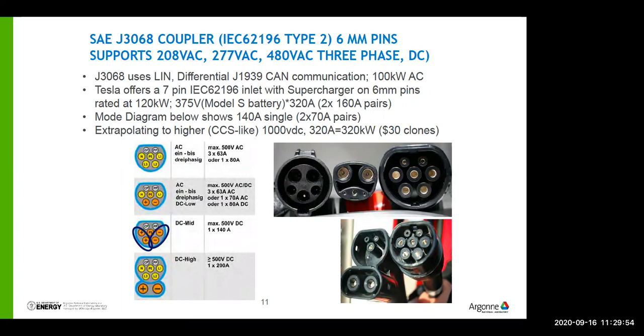That 320 amps at 1,000 volts makes it 320 kilowatt. This, again, not an NRTL listed one, but a clone. These connectors can be had for $30, so it's a very low cost way to get a lot of power. Looking at the header, I can run this at 208, 277, 480 volt 3-phase, or at 1,000 volts DC, same connector. That's a big deal, so just as far as things you should watch out for.